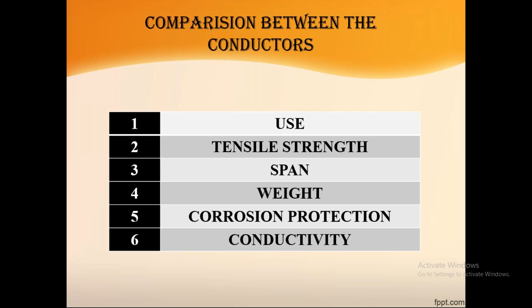The first one is usage. From a usage point of view, the all aluminum conductor (AAC) is used in coastal areas. Why? Because the AAC conductor has high resistance to corrosion, so it won't rust quickly when water drops fall on it. That's why this type of conductor is used in coastal area lines, and it has less weight compared to the remaining two. This conductor has 99.7% purity of aluminum.